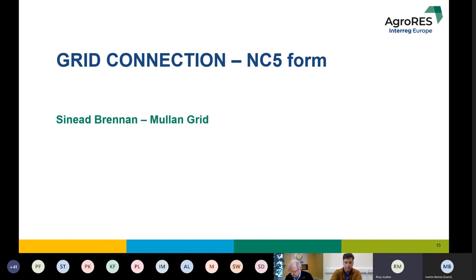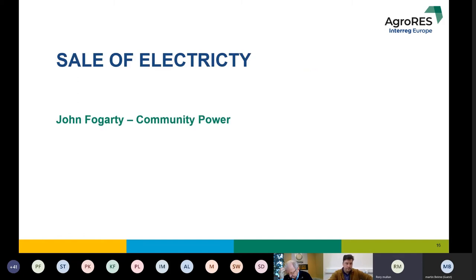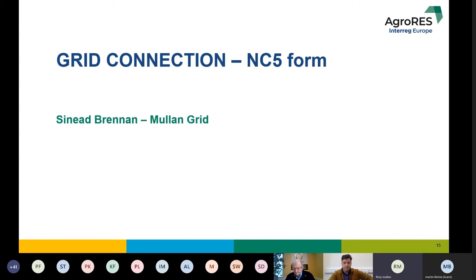So you complete the application form and put in the application fee to ESB Networks, and then they go and process the connection offer and come back. As part of processing the offer, they look to see if the existing local network can cater for that level of export onto the grid. Now, where there's no other generators on the system, most local three-phase networks could probably take up to 500 kilowatts.